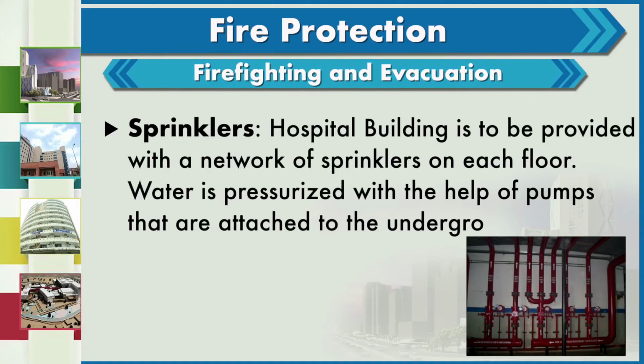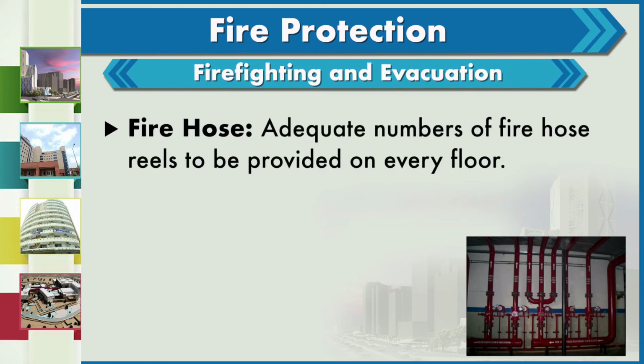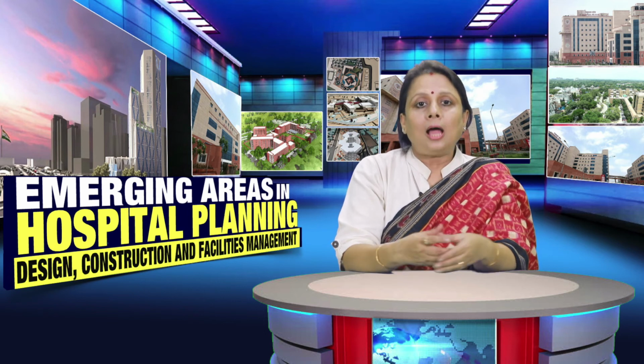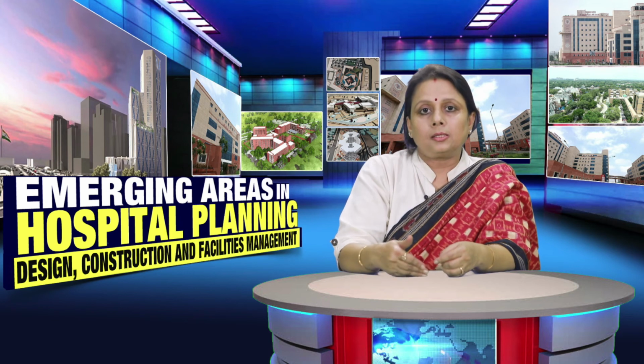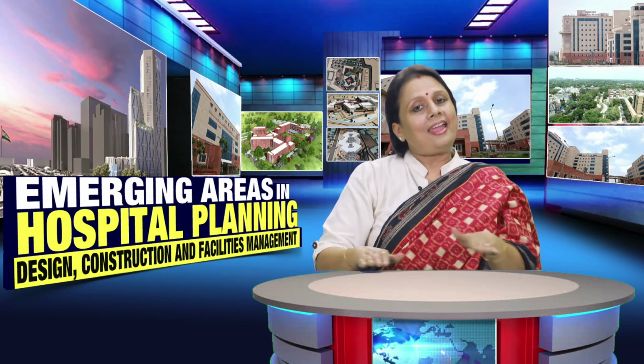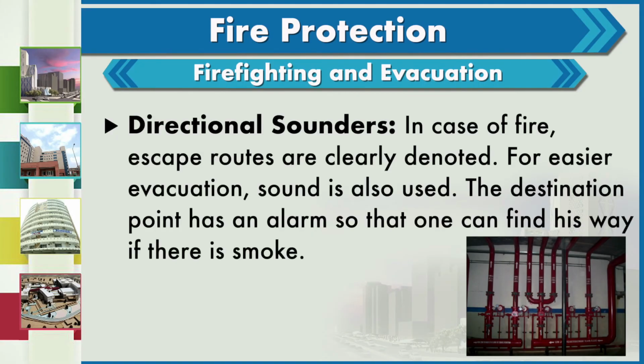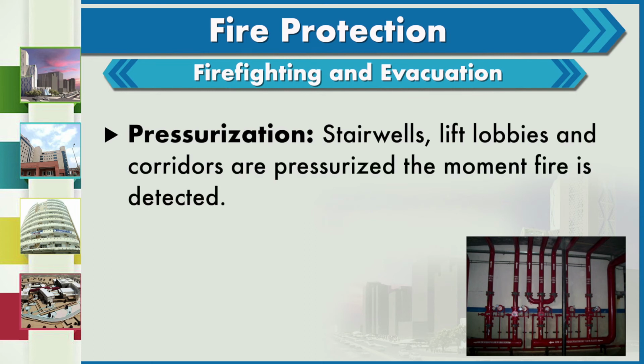For fire protection, we talk of firefighting and evacuation. So, sprinklers is the first thing. Hospital building is to be provided with a network of sprinklers on each floor at regular intervals. Water is pressurized with the help of pumps that are attached to the underground water storage tank. We have to also use fire hoses. Adequate numbers of fire hose reels are to be provided on every floor. Fire hose cabinet or FHC, which house the wet risers, are also located as per the fire circles. An easy thumb rule is to provide one fire hose cabinet near every fire staircase. Directional sounders. In case of fire, escape routes are clearly denoted, and for easier evacuation, sound is also used. The destination point has an alarm so that one can find his way if there is smoke. Pressurization is done for stairwells, lift lobbies and corridors.